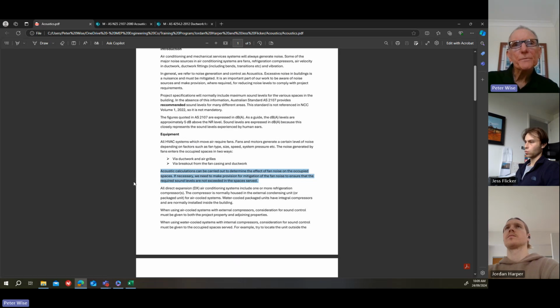And if necessary, we need to make provision for mitigation of fan noise to ensure that the required sound levels are not exceeded in the spaces served. So that's obvious, and you're becoming aware of this now. Over time, you get a feel for it. You start to get a feel for what's the fan noise, how much ductwork have we got, do we need a bit of internal insulation? You don't always have to do acoustic calcs, but in the early days when you're learning, sometimes it's going to help you to do the acoustic calcs, just so you get a feel for what you need to do and whether it's going to be an issue.